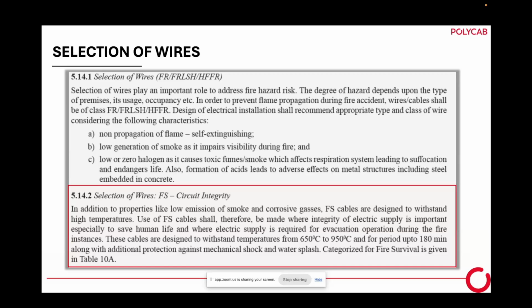Next is selection of wires, FS cable. See here, circuit integrity - the second sentence notes that use of FS cable shall therefore be made where integrity of electric supply is important, especially to save human life, and where electric supply is required for evacuation operations during fire instances. So it's clearly mentioned that it is mandatory. The cables are designed to withstand temperatures from 650 to 950 degrees centigrade for 180 minutes.